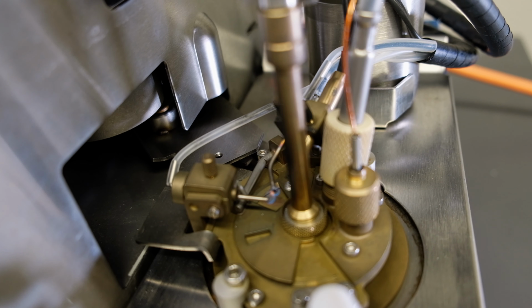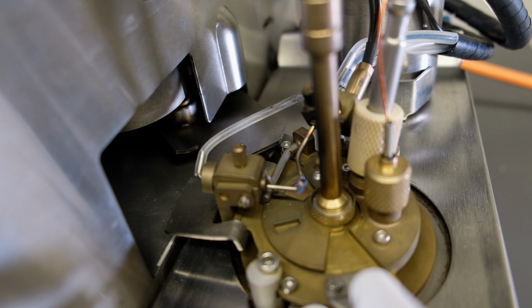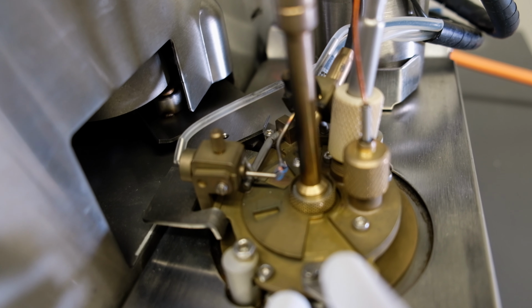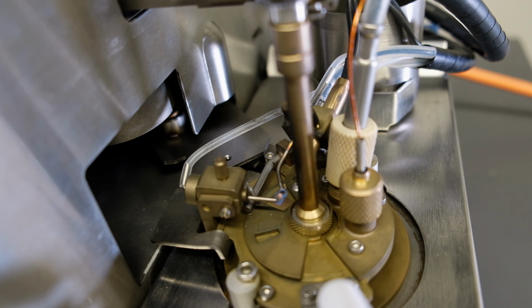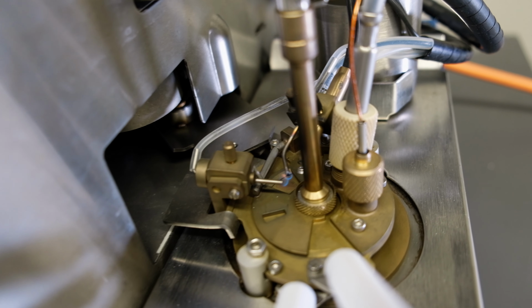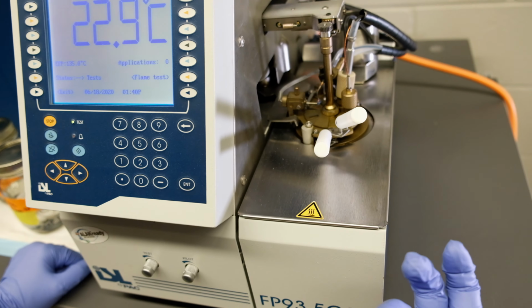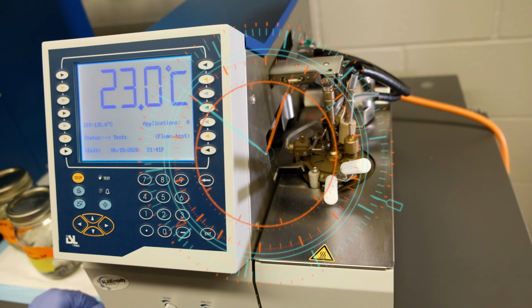And at this point, you just kind of wait and manage the flame and wait for the jacket to heat up. It will start the testing process automatically. And it will open the top, stick the flame in, and then it will quickly close it, pull the flame back out, and reignite the test light.